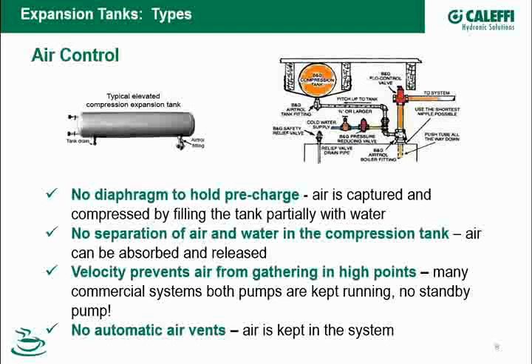So one of the things with an air control system is velocity is key. I have to have enough velocity in my water to entrain the air so that if there's air outside of the tank that's coming out of solution, it can make it back into the boiler. And in this picture on the top on the left-hand side, there's an air control fitting here, and that air control fitting is designed to take those air bubbles and direct them back to the compression tank that's normally installed above the boiler itself. The other thing about these air control systems is there are no automatic air vents. I have to keep the air in the system, otherwise I'll slowly lose the air charge out of the tank. It will waterlog, the release valve will lift, and then I have to recharge the tank itself. So this is air control.